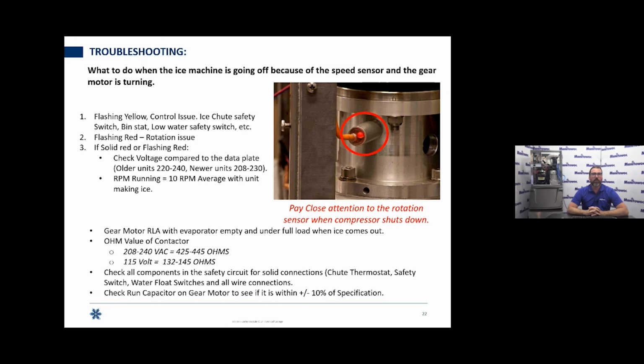Remember that fast flash, 2 flashes per second, means that we sensed an RPM issue, something was going on with RPM with that gear motor. We're going to have to troubleshoot further. Maybe we have a bad gear motor. It's not impossible that we have a bad rotation sensor. So of course we want to verify that we do actually have RPM, that we have rotation. Again, we can see that by unscrewing that sensor. You can see that motor operate when you turn the power switch on. You'll see that auger turn.